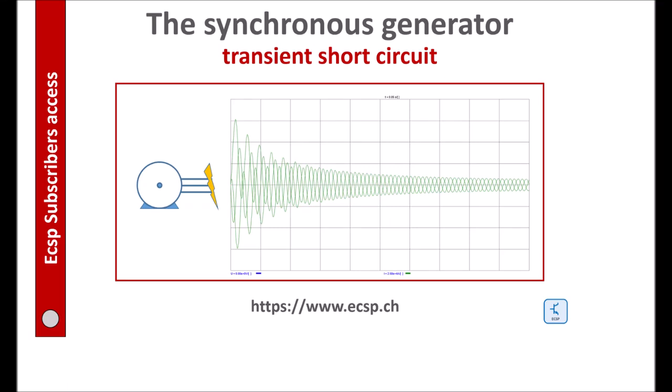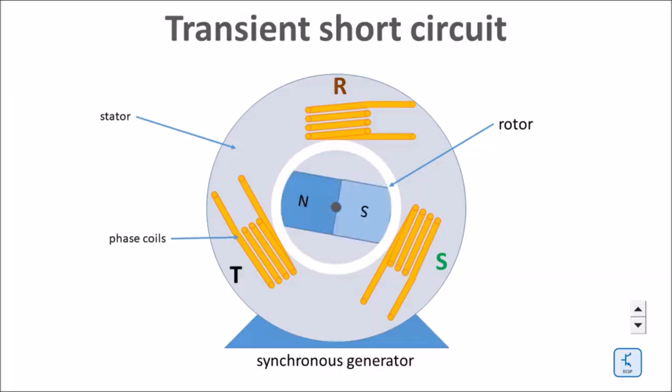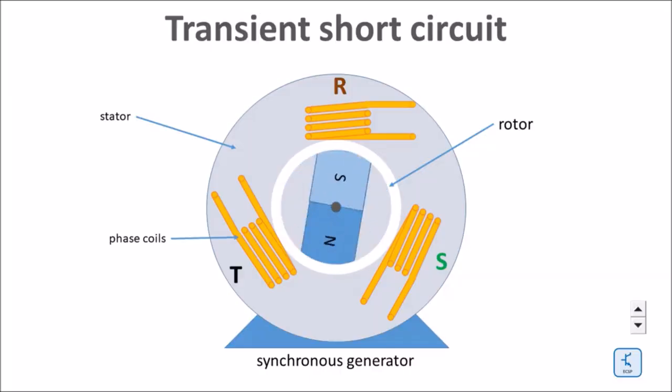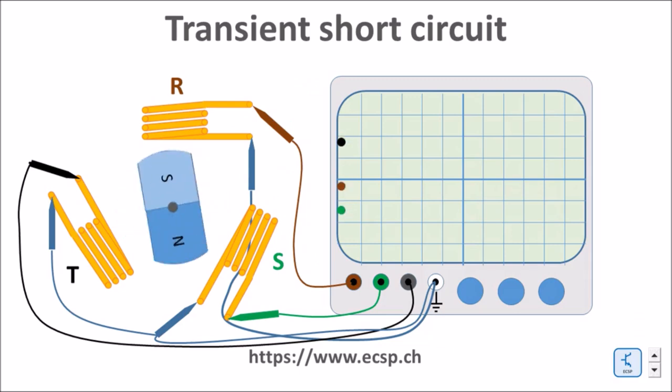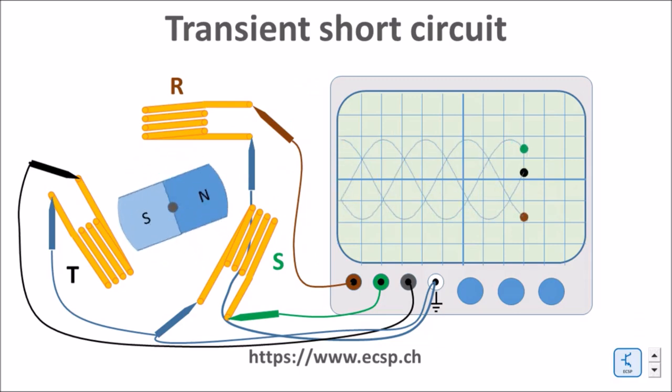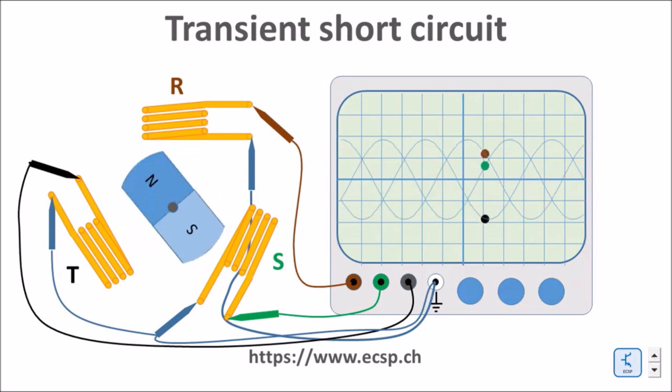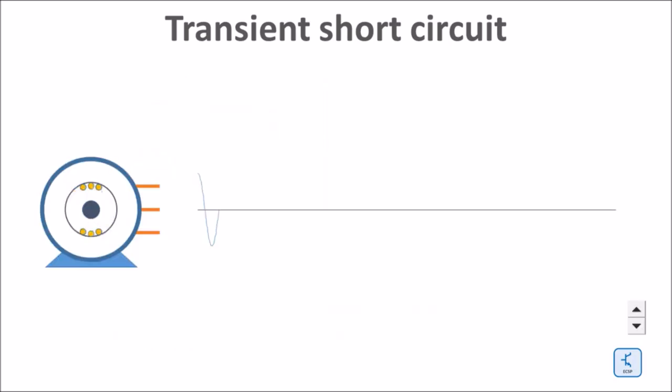Hi everybody, in this video let's discuss the reason for the very high transient short circuit currents in the vicinity of synchronous generators. A synchronous generator consists of a rotating rotor with a constant magnetic field and a stator with three-phase coils. The rotating magnetic field induces a voltage in the three-phase coils.